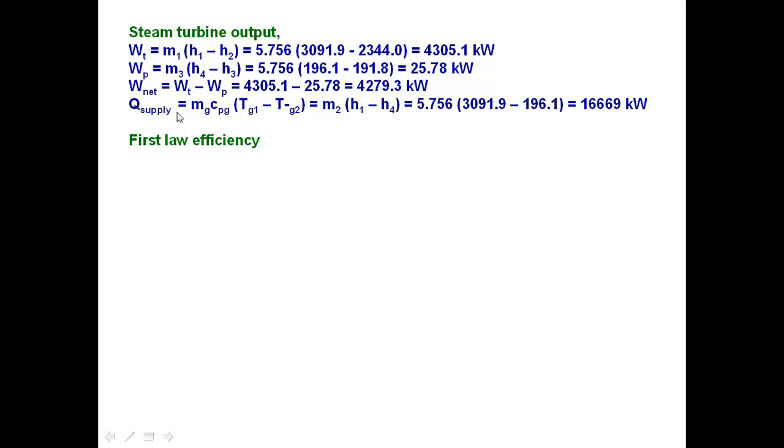The amount of heat supplied to the boiler, that is the heat recovery steam generator, is 16.669 megawatts. The first law efficiency can be calculated from the output by input, the output is net output from the steam turbine.